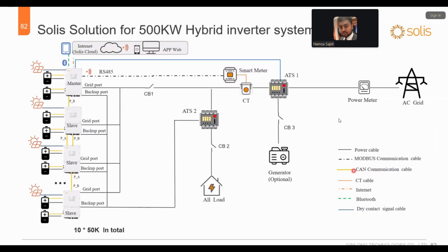Okay, so this is the Solis solution for the 500 kilowatt hybrid inverter system. All you have to do is parallel up the inverters. A separate battery will be installed for each inverter, so it will be easy for you to own and maintain, and even if you need to replace anything, you can do it easily. You need to connect the master PB port and connect with the PA.